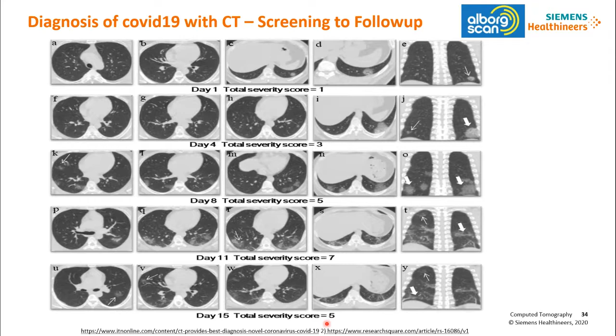What we have done: everybody has a filter in the X-ray. With a patented technology, we add an additional filter called a tin filter. What the tin filter does is reduce the unwanted quanta from the radiation. We conducted some studies about that. Compared to conventional CT, it requires 1/10 of the dose with the tin filter. We don't limit this technology to any one scanner. Whenever we invented this technology, we implemented it in all of our CT scanners. So the tin filter will allow you to do low dose scans, and at the same time repeated scans. It is a really good tool.